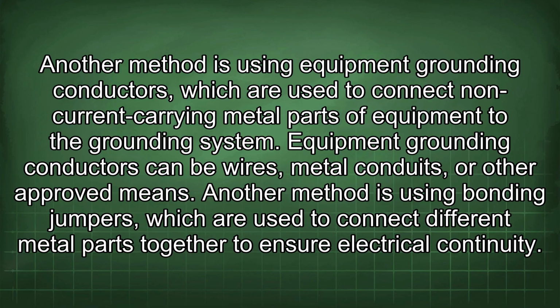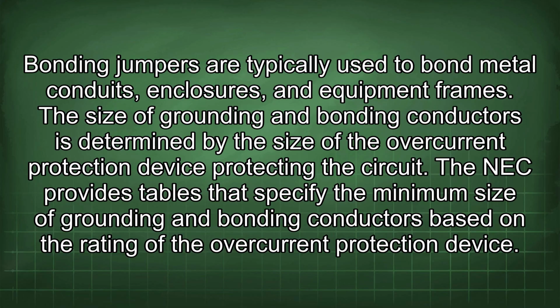Another method is using bonding jumpers, which are used to connect different metal parts together to ensure electrical continuity. Bonding jumpers are typically used to bond metal conduits, enclosures, and equipment frames. The size of grounding and bonding conductors is determined by the size of the overcurrent protection device protecting the circuit. The NEC provides tables that specify the minimum size of grounding and bonding conductors based on the rating of the overcurrent protection device.